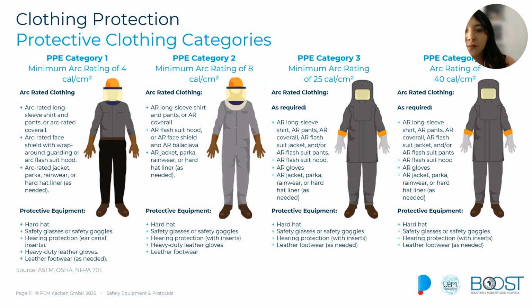We have different standards for defining protective clothing, but according to NFPA 70E, we can classify suits into four categories, from category 1 to category 4, each intended for a maximum amount of released energy measured in calories per square centimeter. The first category is basic protection, where it's usually enough to wear long-sleeved arc-rated shirts and pants, plus additional equipment like safety glasses and gloves.